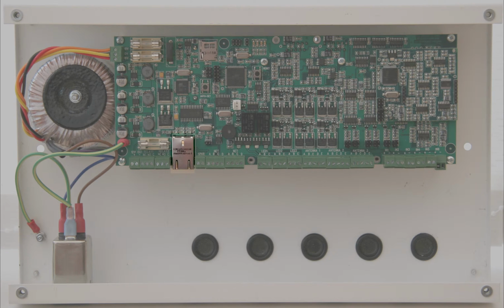To the right of this is the LAN connection for connection to an Ethernet base 10 network. To the right of the network connector is the connector for the loudspeaker. This should only ever be connected to a loudspeaker. It cannot drive a sounder or any voltage dependent device. It can only be connected to an 8 or a 16 ohm impedance loudspeaker.